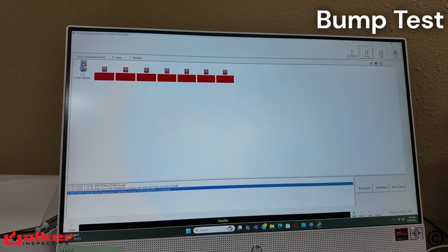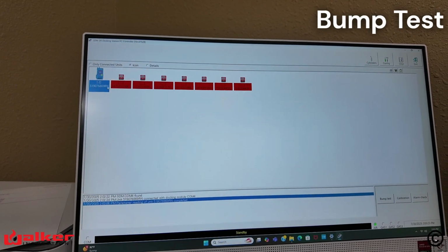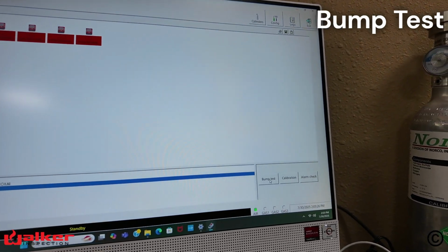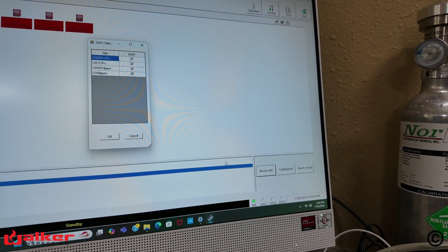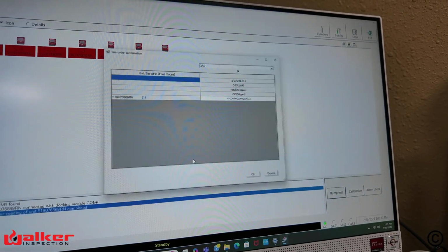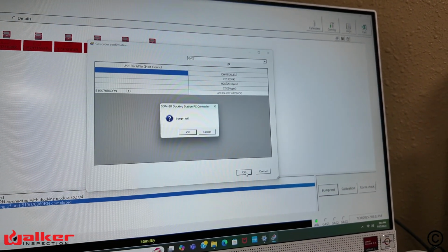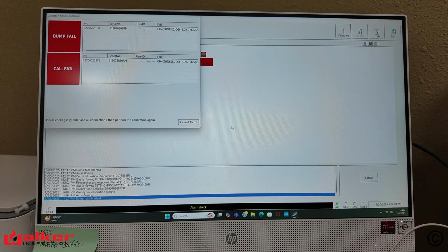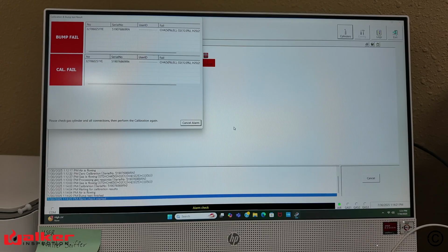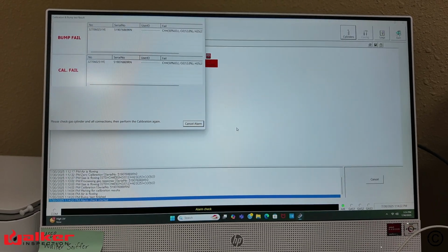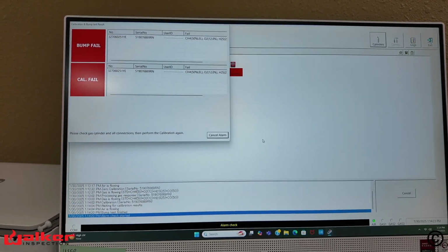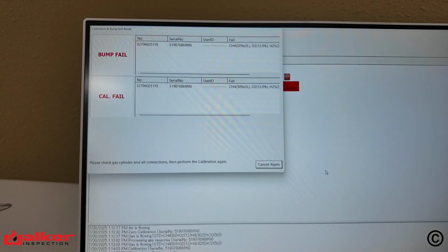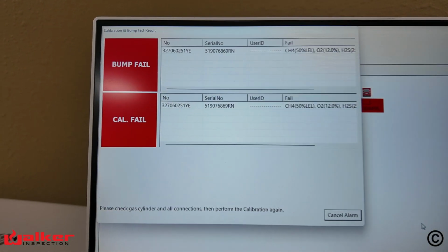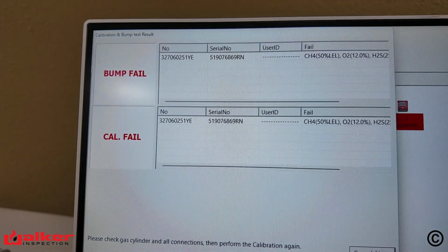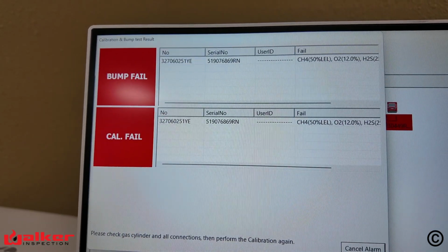A bump test will be the same process as the calibration. The only difference is we will click the bump test button on the bottom right-hand side instead of the calibration button. The bump test is going to be much shorter than the calibration, so it will not take as long. Again, when the bump test has either failed or passed, that will display. As you can see here, this bump test failed. This monitor failed because the filter hose was pinched off on the outside, and the calibration station could not get clean air into the bottle. Continue with troubleshooting processes if your bump test fails.